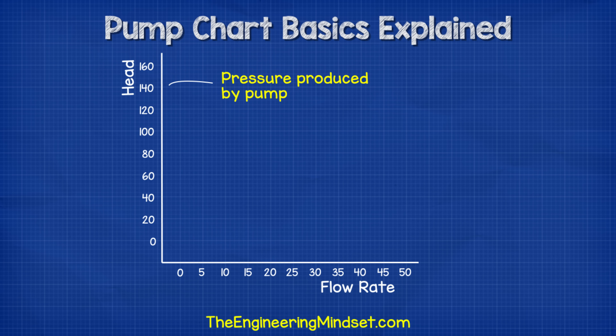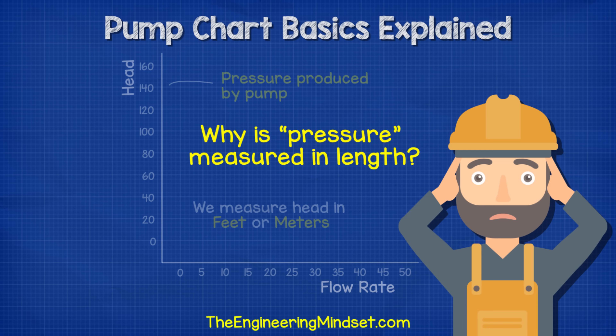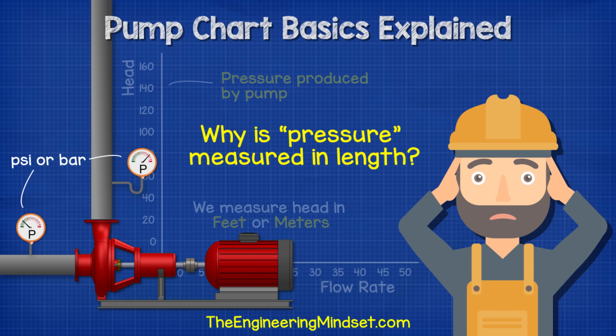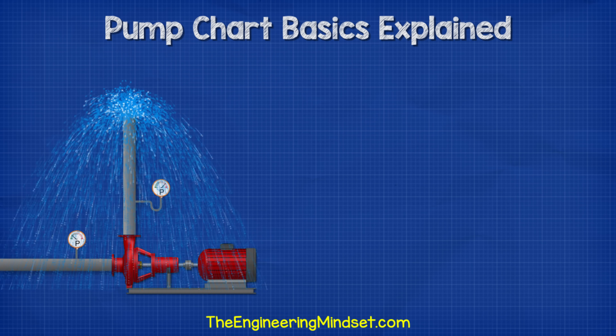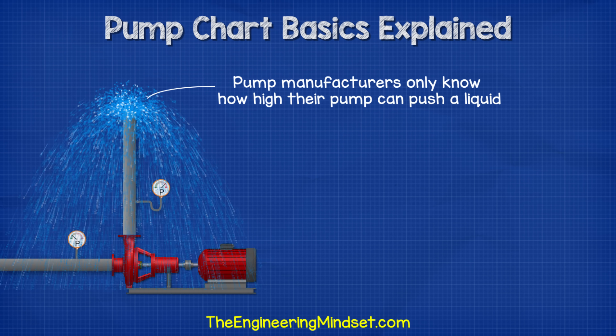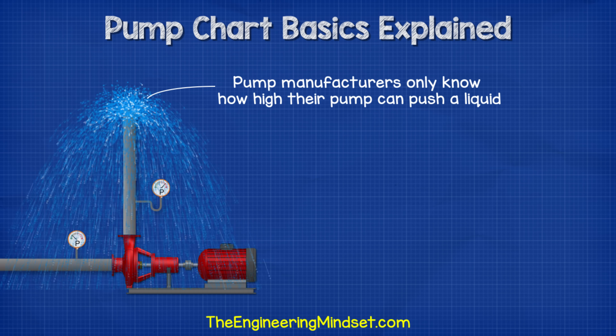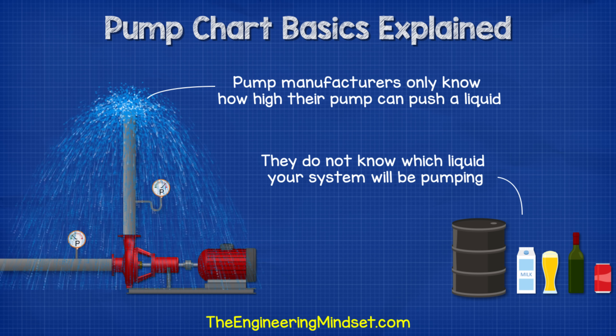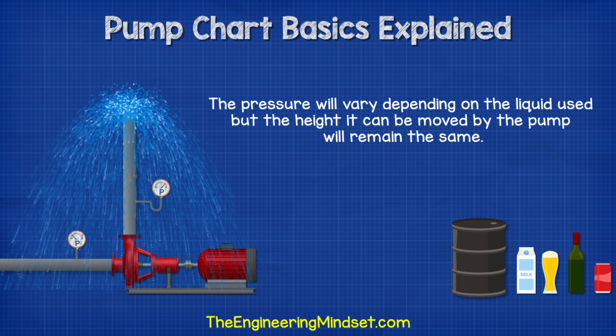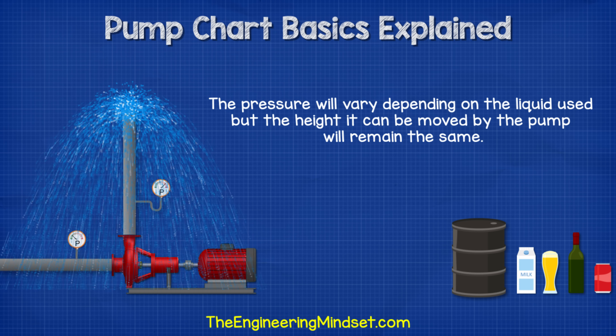Head is shown on the vertical axis and this is referring to pressure, so we often hear the term head pressure. We measure head in feet or meters, which doesn't seem correct considering we're talking about pressure, especially as you see the pressure gauges on the pump typically reading PSI or bar. The reason for feet or meters is that pump manufacturers only know how high their pump can push a liquid — they do not know which liquid your system will be pumping, and as each liquid has different properties, the pressure will vary depending on the liquid used. However, the height it can be moved by the pump will remain the same.